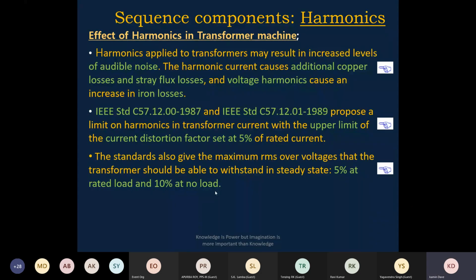The effect of harmonics in a transformer machine: if we apply the harmonics to the transformer it may result in increased levels of audible noise. Similarly, in an induction rotating machine, यहाँ पे भी वो humming sound transformer में ज़्यादा बढ़ेगा इसमें. The harmonic current causes the copper losses and stray flux losses, and voltage harmonic causes an increase in iron losses. Voltage harmonic से iron losses बढ़ेगा and current harmonic से copper losses and stray losses ज़्यादा बढ़ेगा. Ultimately, it is a severe rating issue for the transformers.